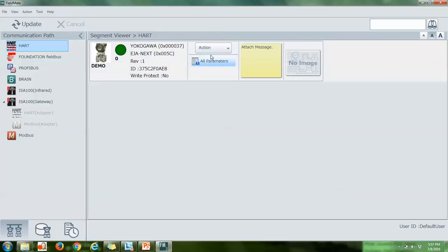I'm going to come back to these two buttons right here. I just want to show you first that we've got a sticky note here. Whenever you connect to this device, it'll remember this unique device, and you can put something on the sticky note, whether it's the last time it was calibrated, any information about the device, maybe if it's in a unique application, or just something you want someone to see. The same goes for an image. You can attach an image, maybe of where it's installed if it's in a unique place. And whenever you pull up this device, you can know, okay, that's the transmitter at that specific location. That's another good tool.